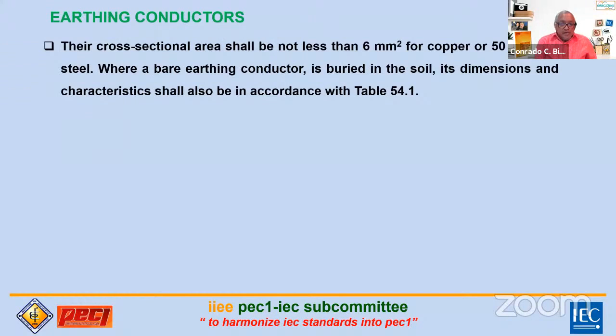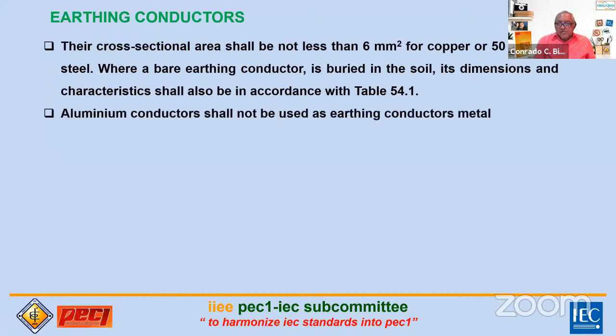So the cross-sectional area of earthing conductors in IEC should not be less than 6 mm² for copper and 50 mm² for steel. So ito yung sa IEC standards. So when a bare earthing conductor is buried in the soil, the dimensions and characteristics shall be in accordance with Table 54.1. So merong guide dito. Aluminum conductors shall not be used as earthing conductors.